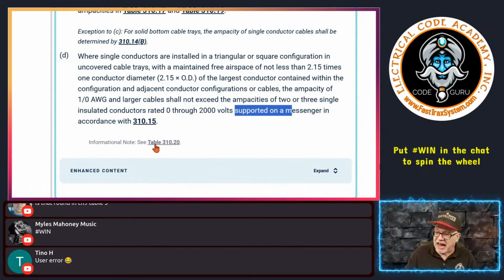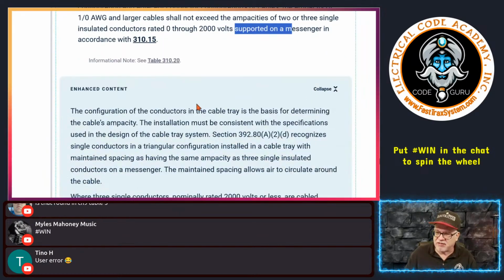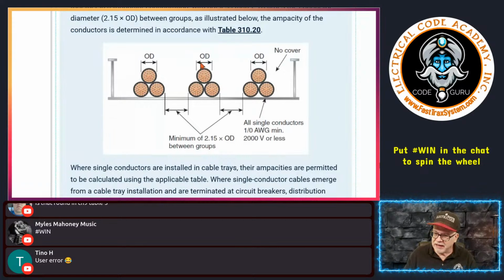Okay, so if I install it like this, and these are connected together, they're plexed together, or configured together, in this case this is a triad, right? Triangle configuration. So if you want to do this in here, and you're, say, an engineer, and you're like, okay, I'm putting plex cables in there, twisting them together, and I need to get higher ampacity, I can buy whatever width tray I need in order to be able to do this. Okay, the tray's uncovered. Gotcha. I need to get a little more ampacity out of these conductors.